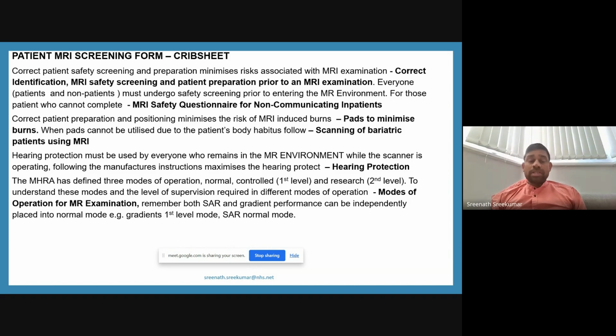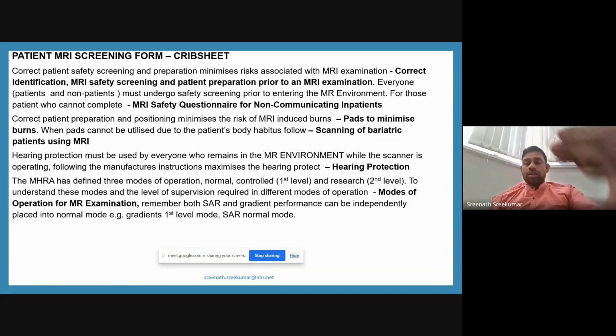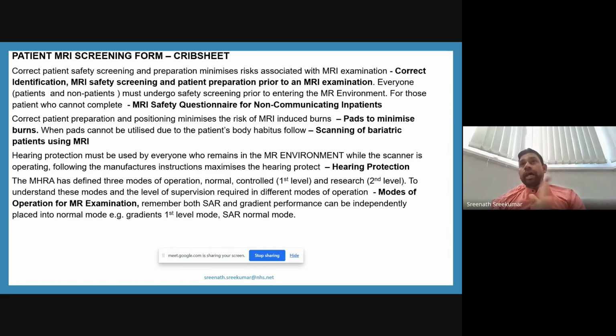Patients must undergo safety screening prior to entering the MR environment. Bringing the patient inside the MR environment and then going through the safety screening is not a safe practice. So we have to follow the safety questionnaire before entering the controlled access area, because wherever the 5 gauss line starts, we have to screen the patient before the 5 gauss line.